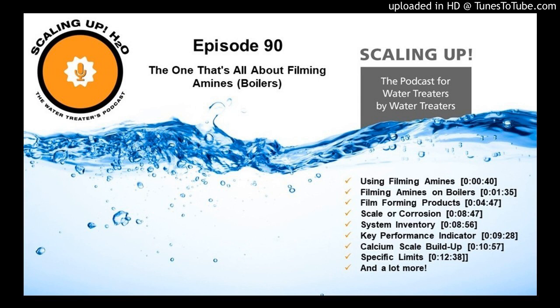If you are in a once through system, unless we are solving a problem, right? Unless we're saving someone a pump every couple of years that they were having to repurchase. So unless there's some sort of issue that we can really fix, I would say once through systems are, with filming technology, expensive. So for a program that's running well and your corrosion rates are good, but you don't really have a great return, I would say that this is maybe not your best option. Really, in a boiler, those are my two biggies.